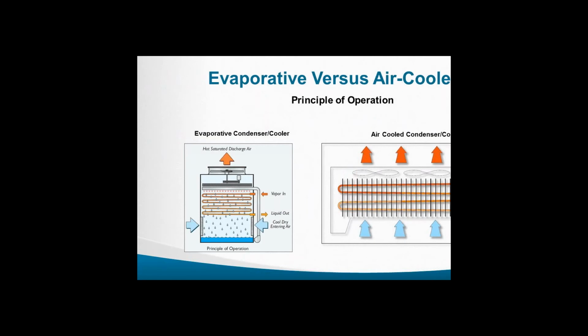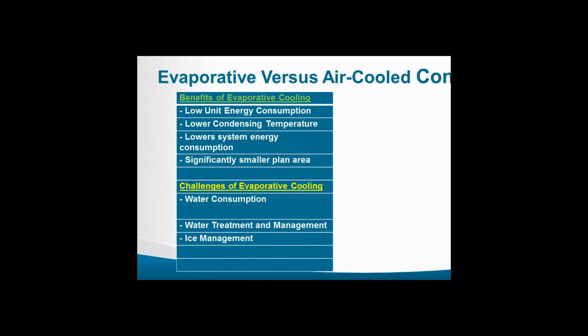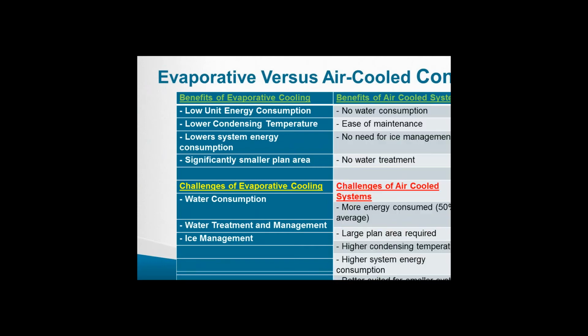So let's look at the combination, or you know, the evaporative versus air-cooled. The benefits of evaporative cooling: it's low energy use. You have lower condensing temperatures on your system, which gives you overall system energy reduction, and it has a small plant area. But it uses water, it has water treatment. You've got to maintain that water. And then depending where you're located, you have an ice management situation.